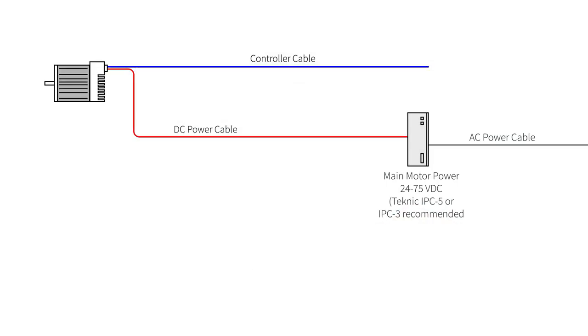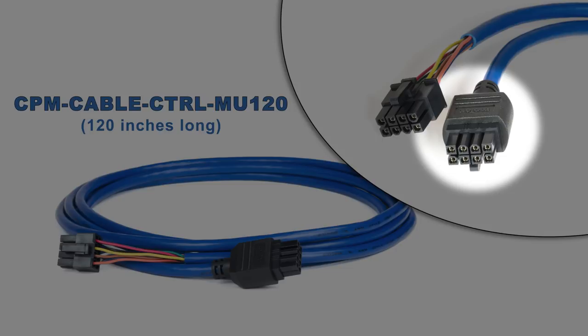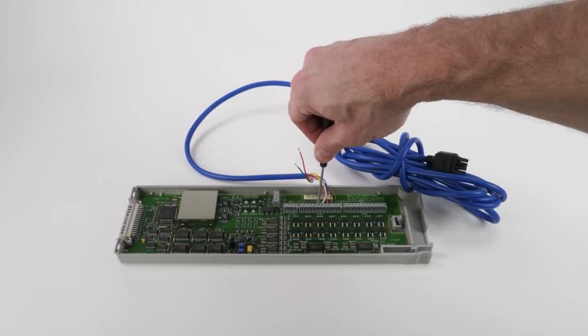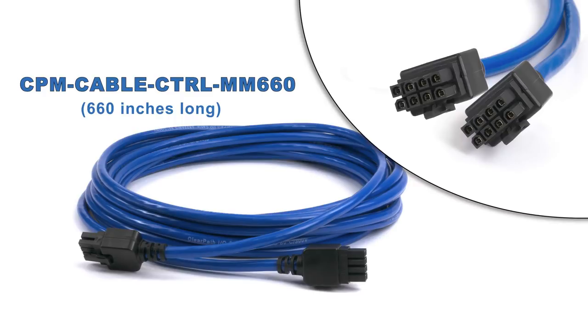The next cable is the controller cable. It connects ClearPath to your third-party step and direction indexer. Teknic offers two controller cable options. The first is a 10-foot cable with 8-pin Molex Minifit Junior connectors on both ends; the motor end is over-molded for water and dust resistance. The other end has a regular connector used to test each cable at the factory, but most people will cut it off to connect the individual wires to their control signals. The 55-foot cable has over-molded connectors on both ends, allowing you to cut it into two cables, each with an over-molded connector at the motor end.